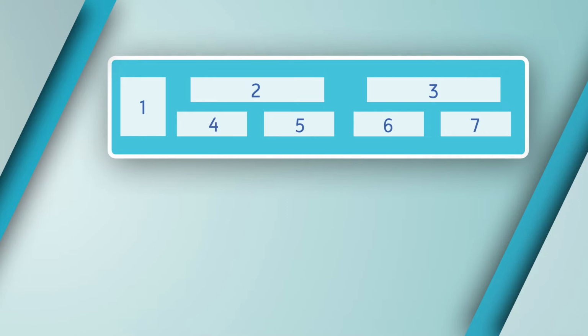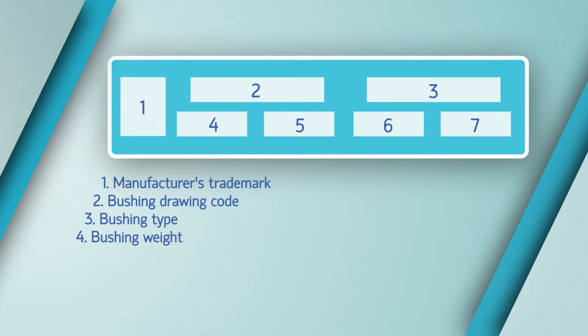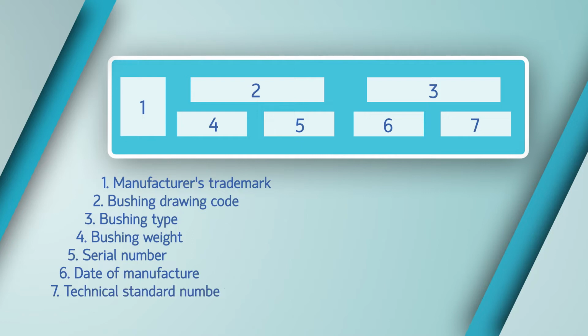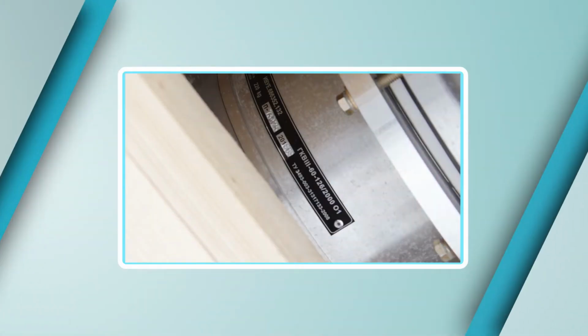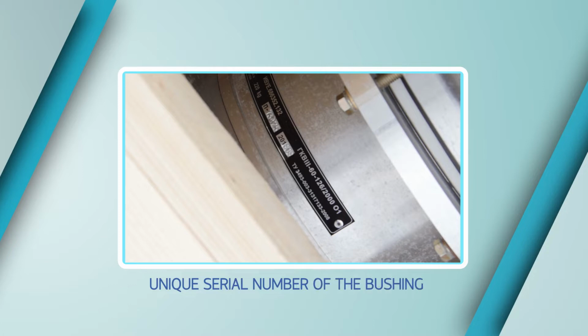The nameplate indicates manufacturer's trademark, bushing drawing code, bushing type, bushing weight, serial number, date of manufacture, technical standard number. Take a look at the unique serial number of the bushing. It has been made by means of punch marking. That is why, in case all other data are lost, this number will help restore all the bushing information required, starting from its date of manufacture up to factory acceptance testing results.